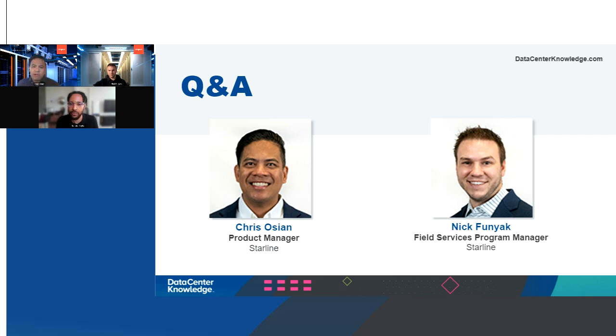I think that might be more of a service-related question. Nick, can you field that one? Yeah, absolutely. From an electrical standpoint, it really depends on the region you're in. We see a lot of ductor testing internationally in Europe, but domestically here in the U.S., an insulation resistance test at 1,000 volts is good for checking insulation breakdown, making sure nothing was damaged during install, and also just a good continuity check.